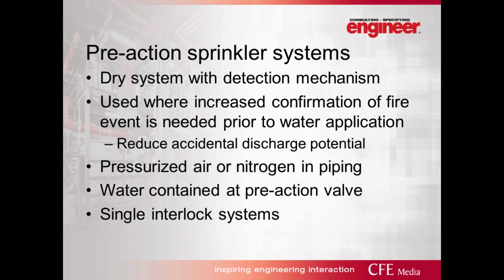In a pre-action system, if that sprinkler is damaged or activated, you won't necessarily get water applying until the detection mechanism also occurs. Similar to a dry system, pre-action sprinkler system piping is typically pressurized with either air or nitrogen, and the water, similar to the dry system, is contained back at the pre-action valve, so that the system piping overhead with the sprinklers does not have any water in it.